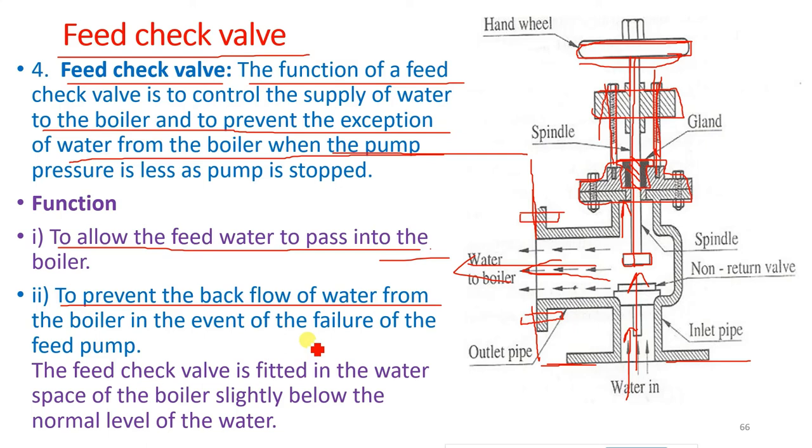If the feed pump is failed, this feed check valve does not allow water from boiler to revert back to the hot well. So it allows water to move in one direction only, therefore it is called as a non-return valve.